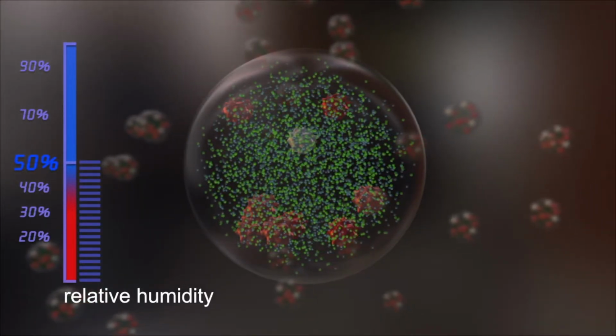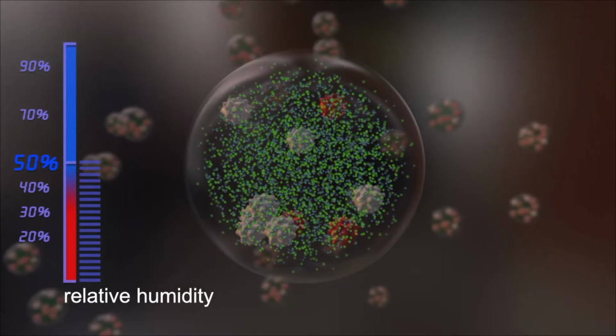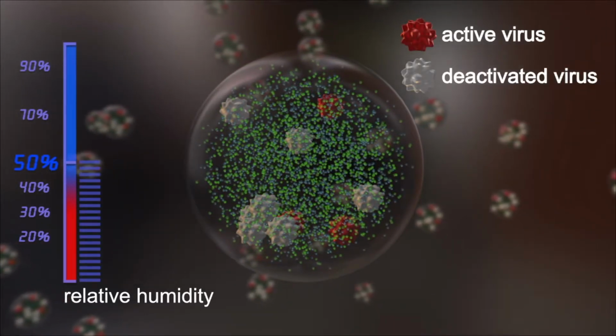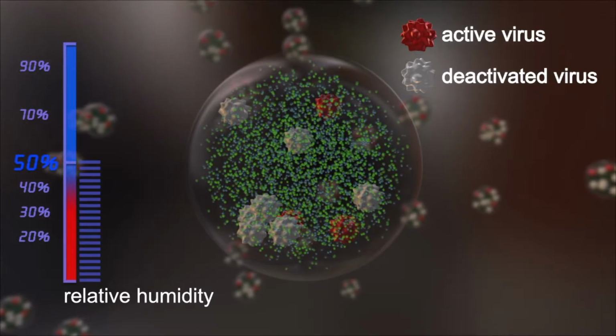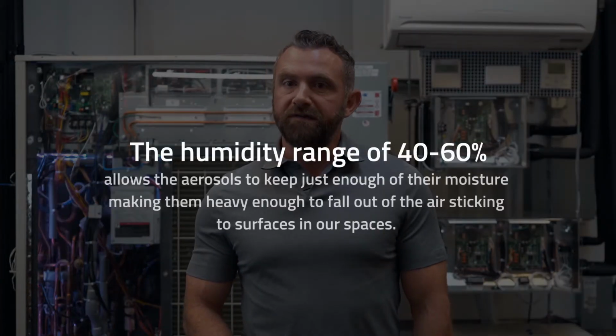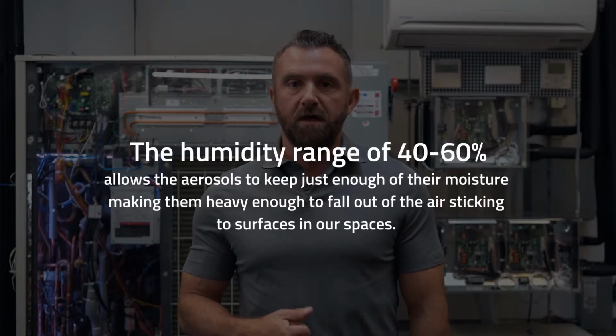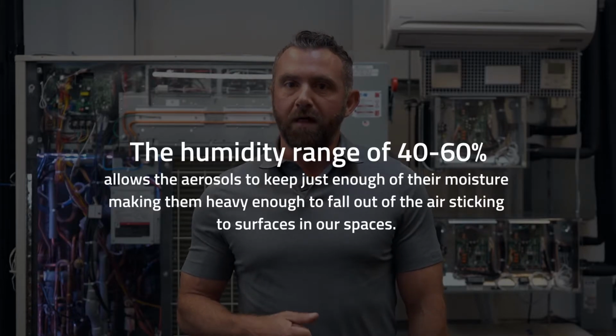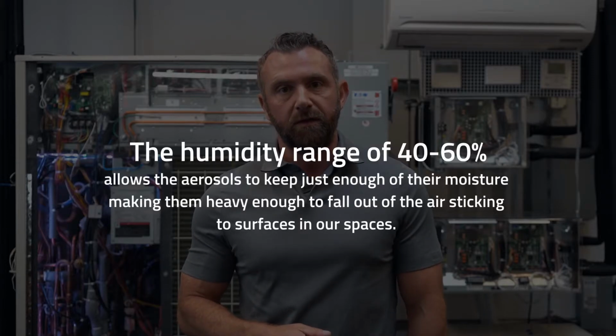If the room air relative humidity is in the optimum range for human well-being, the salt concentration rises to a level where most of the viruses cannot survive and become deactivated. This dramatically decreases the risk of infection. The humidity range of 40 to 60% allows the aerosols to keep just enough of their moisture, making them heavy enough to fall out of the air, sticking to surfaces in our spaces. The bonding forces between the water content of the wet aerosols keeps the viruses attached to surfaces they land on, which prevents them from being swept back up into the air. This lowers the chance that we'll breathe in an infected aerosol.